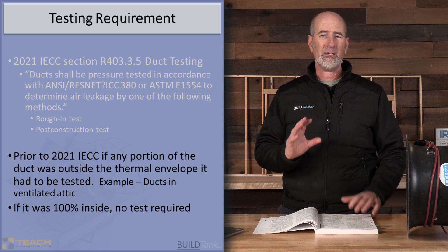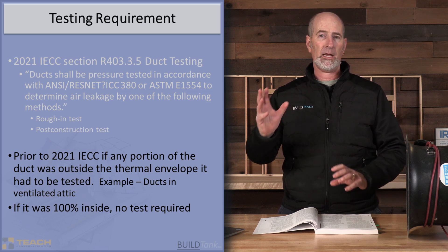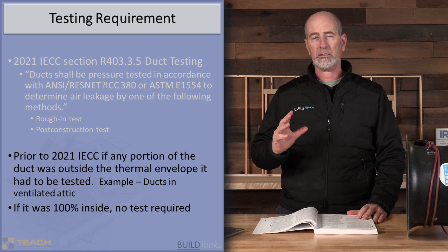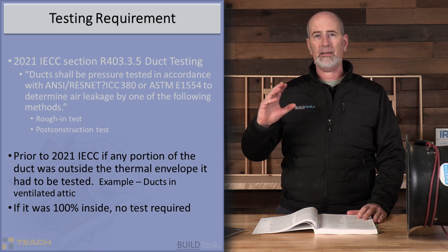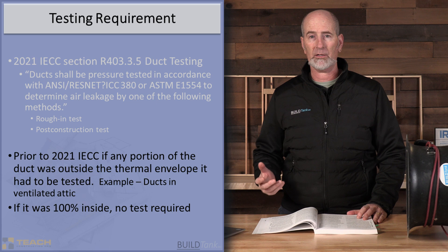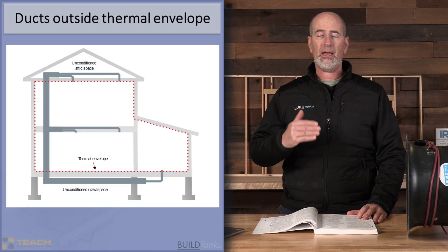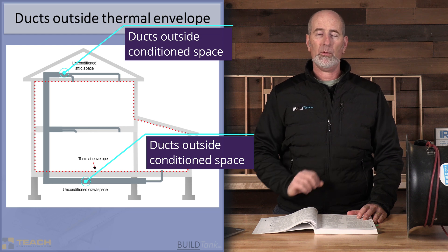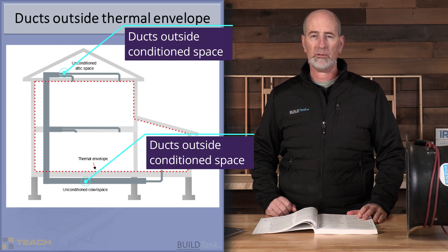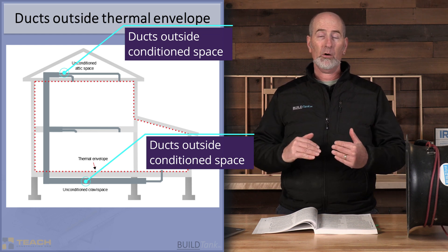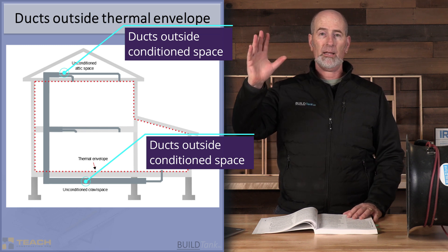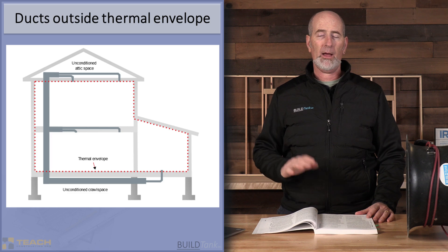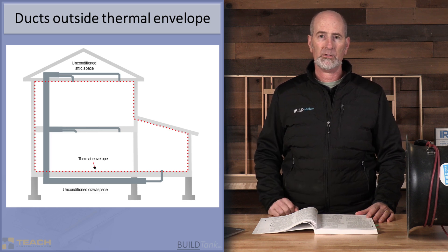A simple way of thinking about ducts outside the building thermal envelope would be thinking about a piece of duct system that is in a ventilated attic, for example. If any portion of that duct was in a ventilated attic in the past, that's when you had to do your total duct leakage test. Now, regardless of whether there are ducts in a ventilated attic or ducts inside the conditioned space of the house, you have to test for total duct leakage.